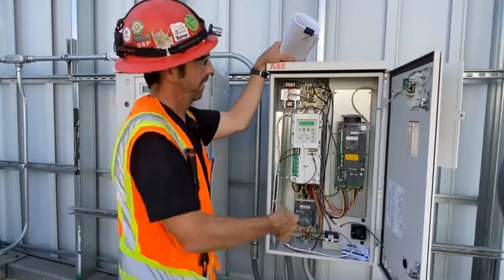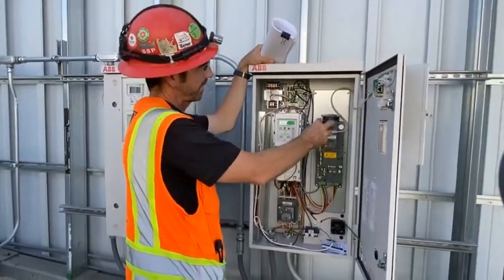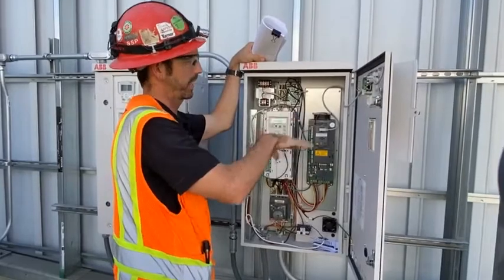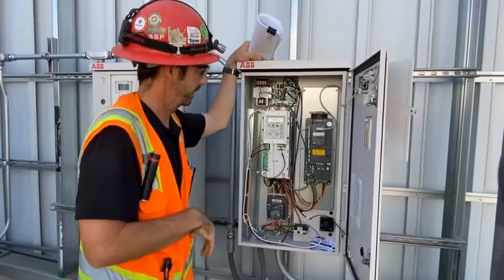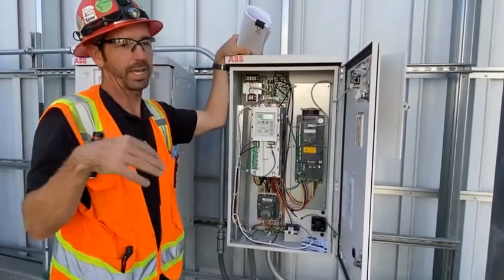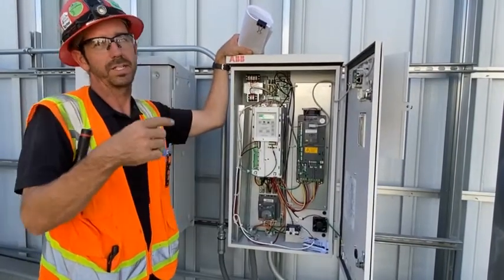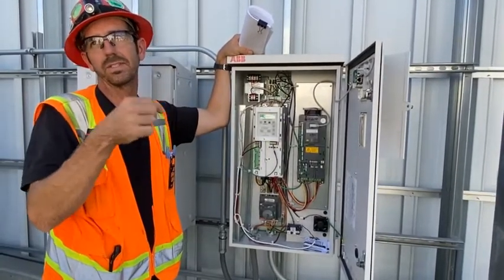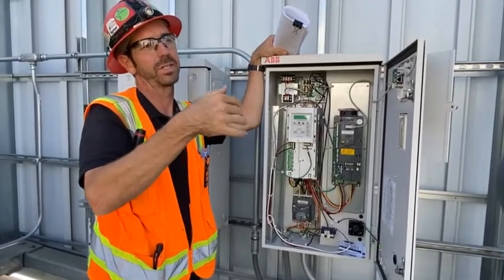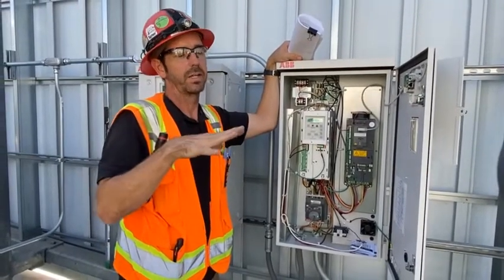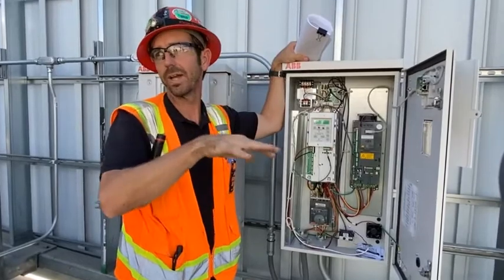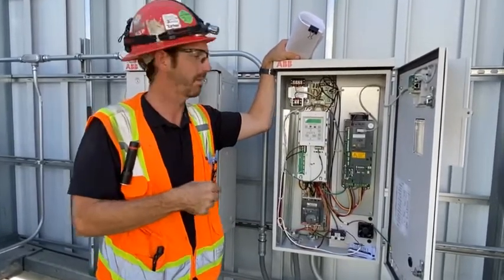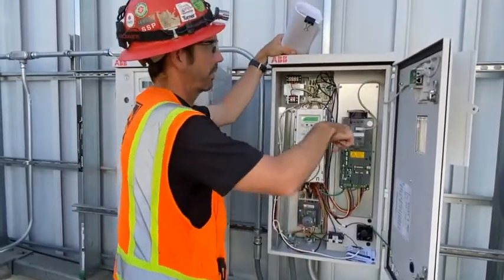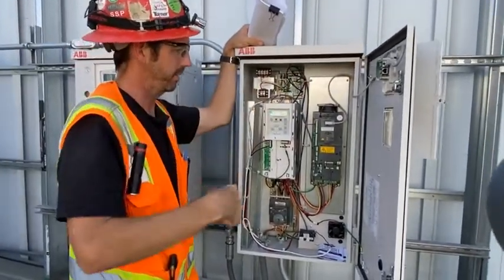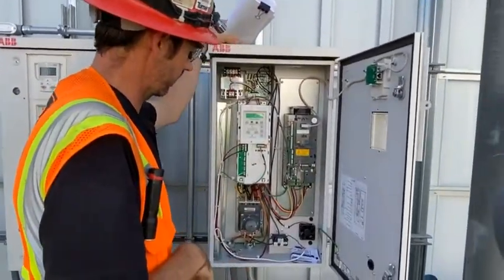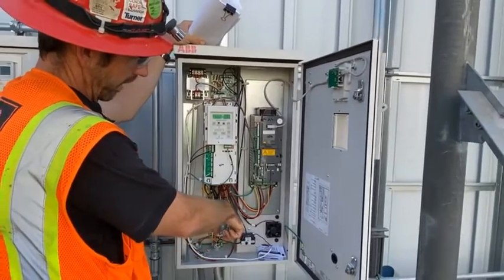Okay. So this device over here is the actual drive itself. This is what adjusts the frequency that goes out to the motor. VFDs take AC input, they create DC power, and then on the output of the DC, they chop up that DC signal, and that creates a modified AC sine wave that then changes the speed of the motor. Okay. Communication cable right here to the keypad, so you can see it with the front door being closed. The BMS is monitoring current status here.